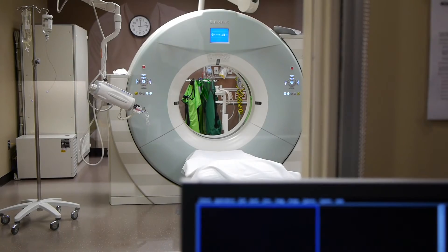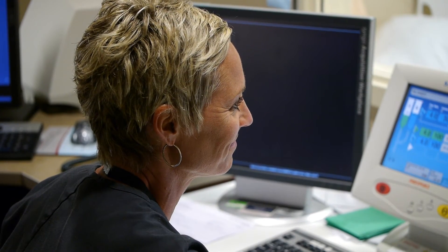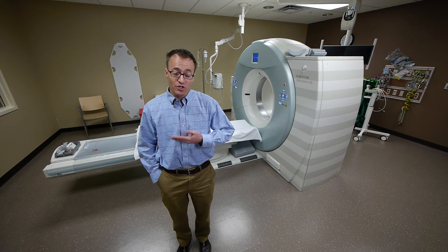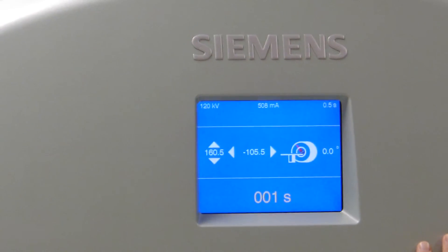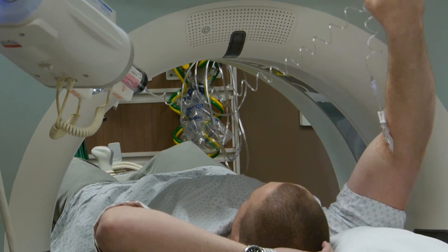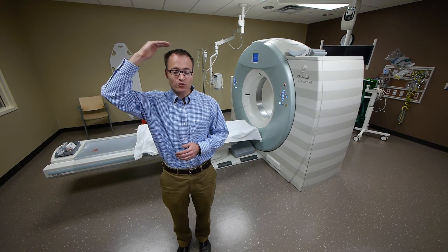There are safeguards built into the scanner designed with patient safety in mind. They require one more button click and can sometimes be an annoyance, but they're critically important to ensure we're asking the right questions: can we reduce dose any more? Can we still get good quality images at low dose? We are actively reducing dose by lowering the overall scan dose as well as having the scanner monitor dose during the scan. For example, the scanner will not administer radiation at the very top of the patient's head — it starts the dose only when it detects the head is in place. Many scanners emit active radiation above the patient's head, but this one does not. That incremental one or two seconds of scanning air actually results in a fairly significant amount of scatter dose the patient can receive. It's little things, but the technology in newer scanners available today is really amazing.